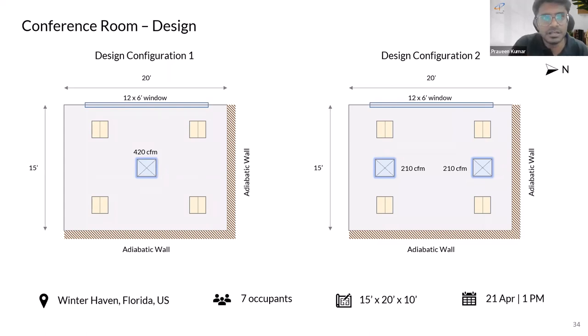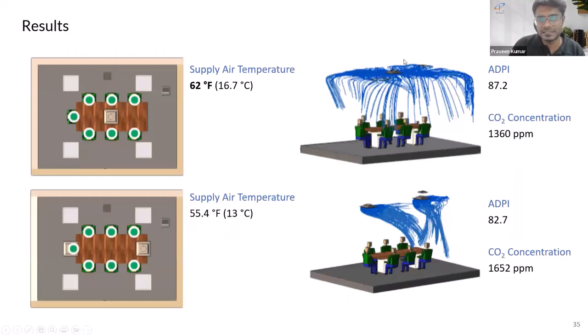This is a conference table meeting room, located in Florida. We are experimenting with two design configurations: one is the centered square plate diffuser with a higher flow rate, 420 CFM, a 2x2 square plate diffuser. The same space is also fitted with two centered square plate diffusers at 210 CFM each, both on the left and the right. So we got some interesting results.